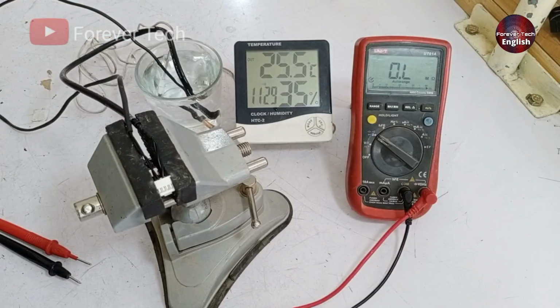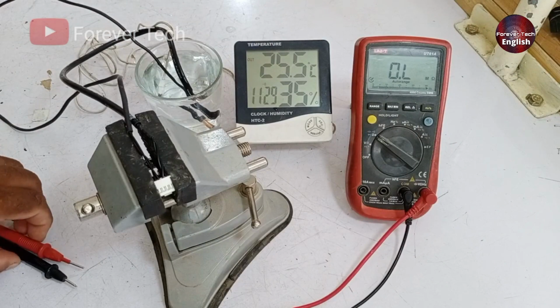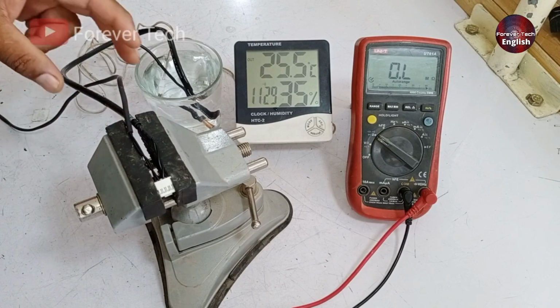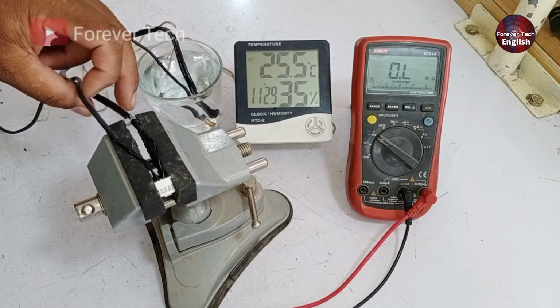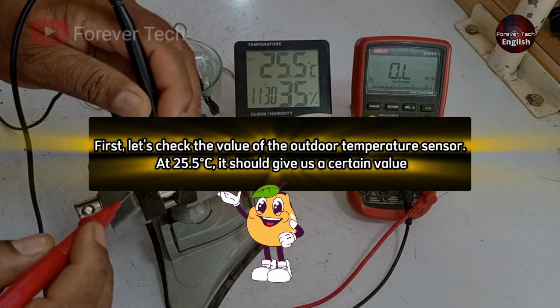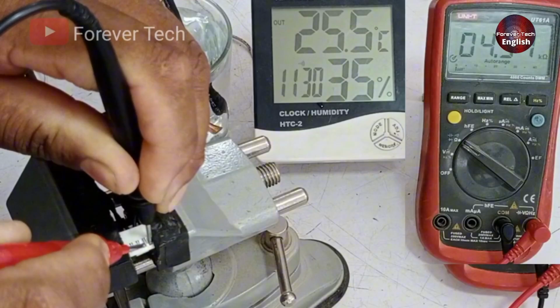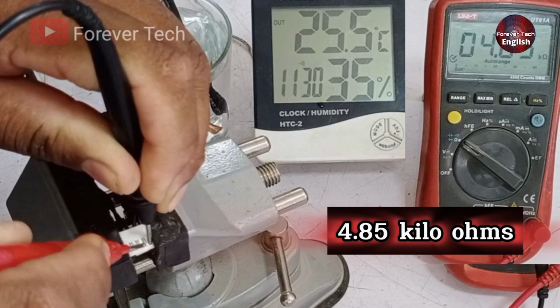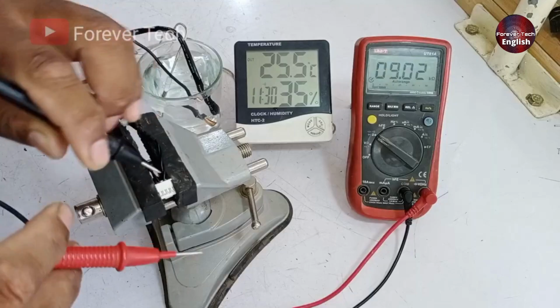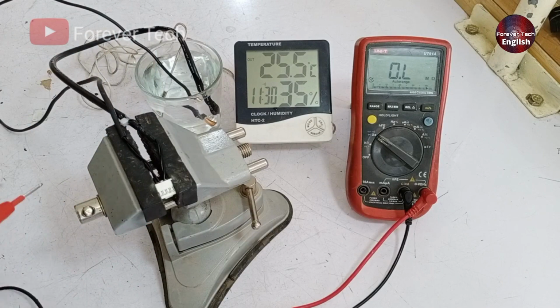It's been a sufficient amount of time, about 10 to 11 minutes. Now, I will check the resistance values. As you can see, I've maintained the water temperature as well. First, let's check the value of the outdoor temperature sensor. At 25.5 degrees Celsius, it should give us a certain value. The reading is approximately 4.85 kilo ohms. If it's around 5 kilo ohms, it's within the acceptable range.